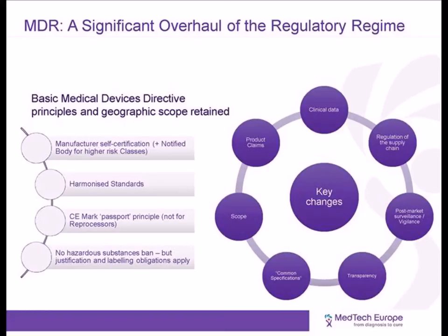And final point on this slide is product claims. Advertising and claims for medical devices are now, for the first time, directly regulated by EU medical devices legislation. And this is on top of existing European advertising rules. Misleading claims made to patients or users with regard to the device's intended purpose, safety, or performance are all prohibited. The MDR therefore expressly prohibits not only off-label promotion of a product, but also more nuanced implications about a device's safety or performance profile. And in particular, creating a false impression about a device's treatment or diagnostic properties, or a failure to inform about likely risks associated with the device, are expressly prohibited.